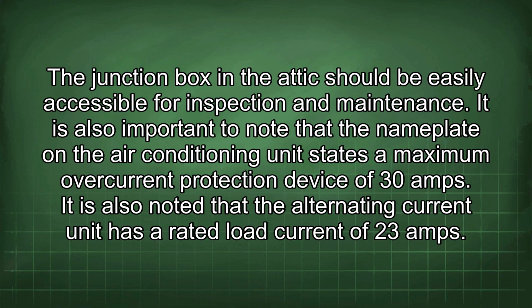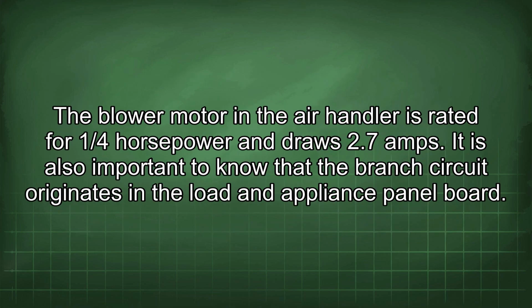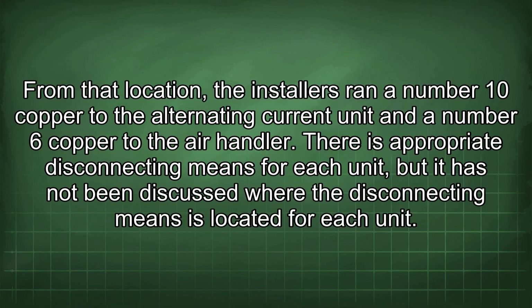It is also important to note that the nameplate in the air conditioning unit states a maximum overcurrent protection device of 30 amps. It is also noted that the alternating current unit has a rated load current of 23 amps. The blower motor in the air handler is rated for 1/4 horsepower and draws 2.7 amps. It is also important to note that the branch circuit originates in the load and appliance panel board. From that location, the installers ran a number 10 copper to the alternating current unit and a number 6 copper to the air handler. There is appropriate disconnecting means for each unit, but it has not been discussed where the disconnecting means is located for each unit.